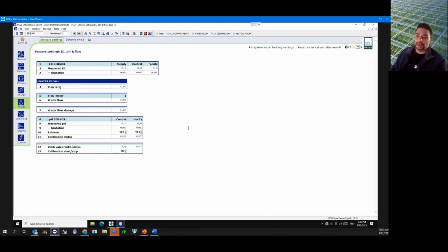It's really important that when you put it in the 7 pH solution, you let it sit there for a couple of minutes, right? This page won't show you much. There's a tool that typically just Priva uses, or maybe your dealer might know how to use it, where we can actually see the measurements start to level out. So we usually wait on that, and I will say it's usually 2 or 3 minutes before there's not as much fluctuation, and so that measurement levels out.